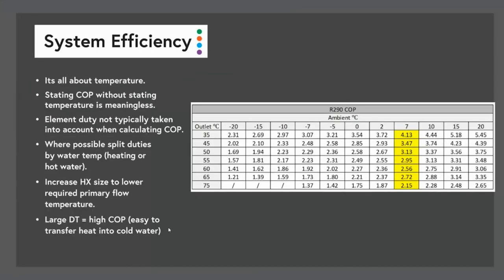Right, moving on to the next one, system efficiency. So typically a very confusing area for most people with heat pumps. So I thought I'd cover this with some detail to try and allow everyone to get their head around it. So when it comes to system efficiency, it's all related to temperature. And only two things define the heat pump efficiency: outside air temperature and flow temperature. Whenever someone says my heat pump is 400% efficient, the question to ask is, at what temperature is that achieved? If they can't answer that question, then their statement is meaningless, because without knowing the temperature combination, the efficiency is unknown. And it varies wildly.